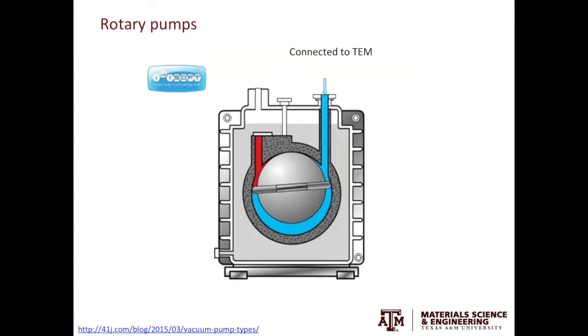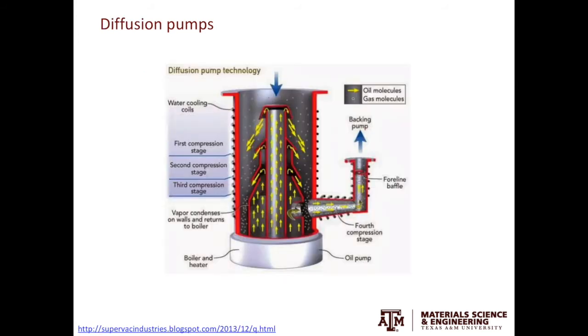The second type of pump is called the oil diffusion pump. Unlike the rotary pumps, the oil diffusion pumps have no moving parts. In the oil diffusion pump, you have the oil reservoir at the bottom and you heat that up to generate oil vapor. As the very fine oil droplets travel in the oil pump, they will grab the air molecules and condense on the pump wall. By removing the air molecules, you improve the vacuum of the system.